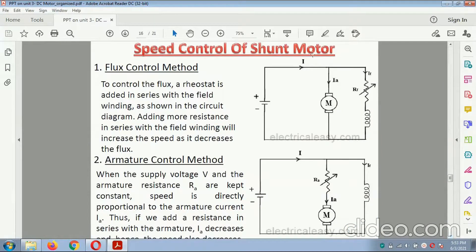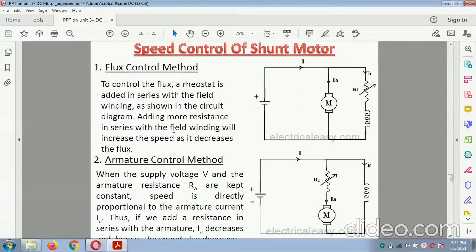Speed control of the shunt motor — flux control method: to control the speed of the shunt motor using the flux control method, a rheostat is added in series with the field winding. Adding more resistance in series with the field winding increases the speed and decreases the flux. This is the rheostat and the shunt winding shown in the diagram.